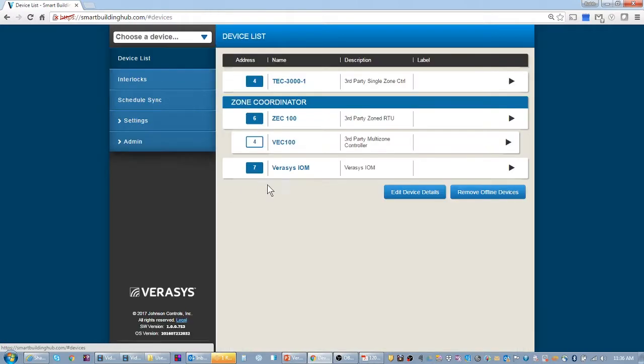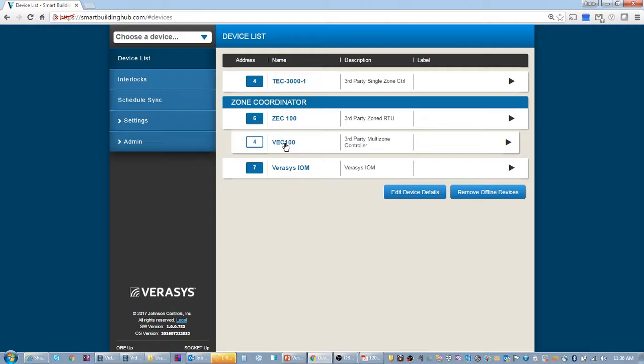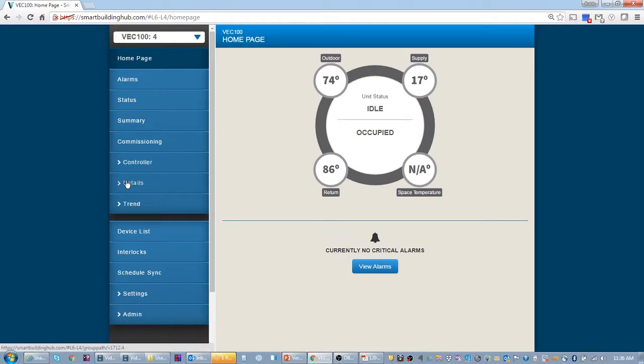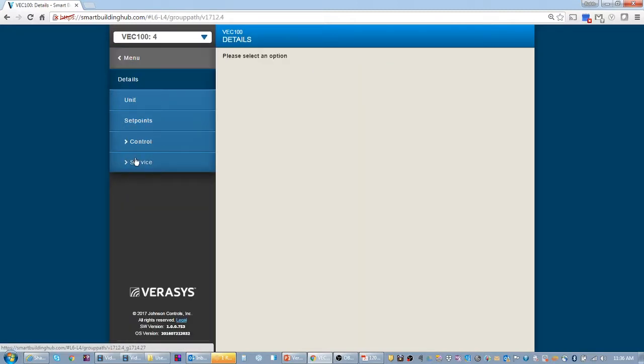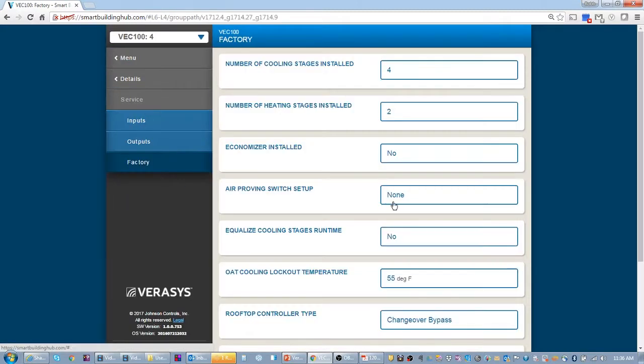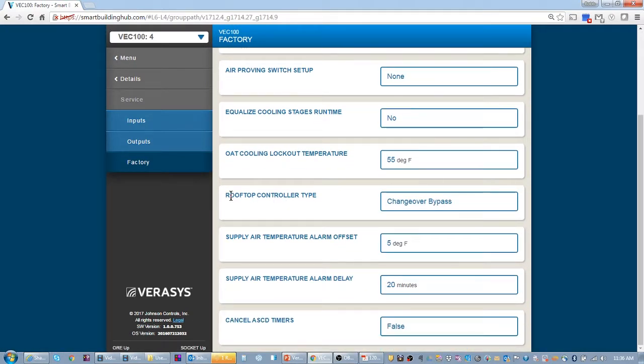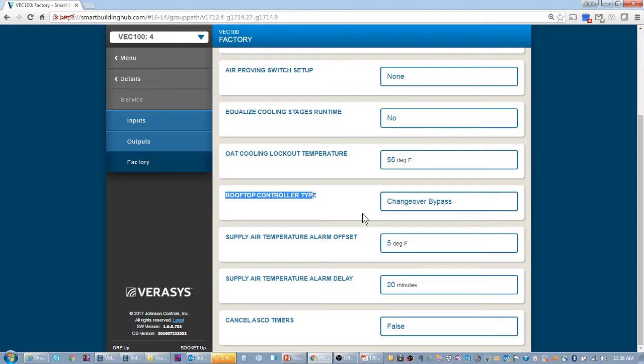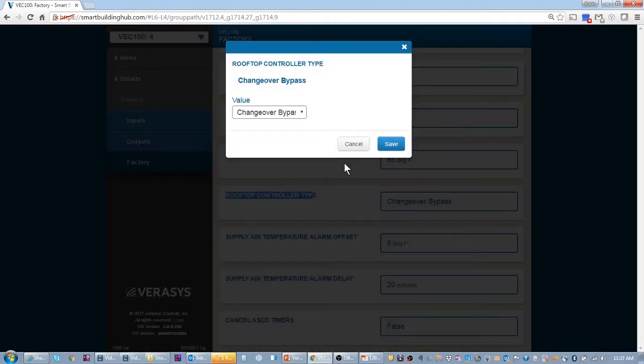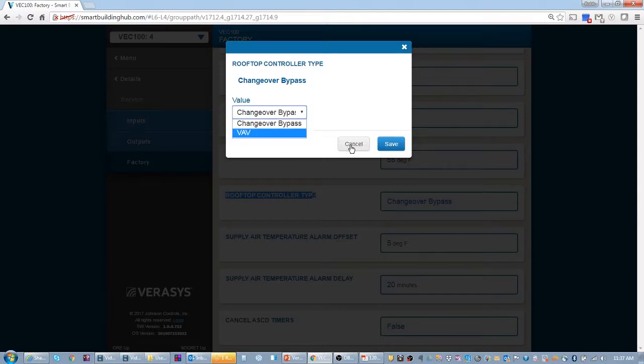That is how you switch your zone coordinator to go from VAV to changeover bypass. It's all done through the unit, whether this is a third party multi-zone unit or whether it's a smart equipment unit. It is literally the same technique. You would go to both controllers, details, service, factory, and you're going to look for the rooftop unit controller type. That sets whether it's VAV or changeover bypass. The smart equipment unit has a couple more parameters in here besides VAV or changeover bypass and you can ignore those.